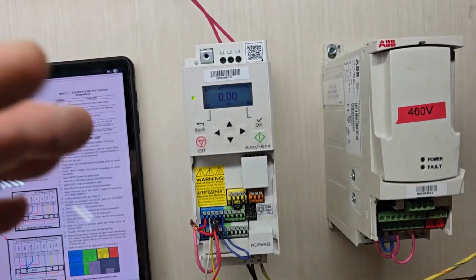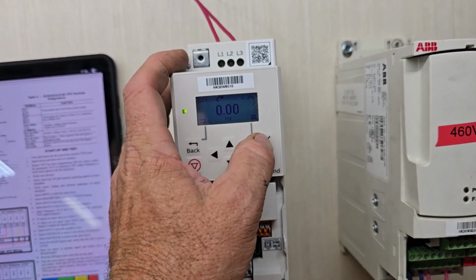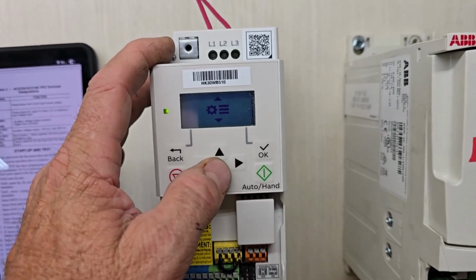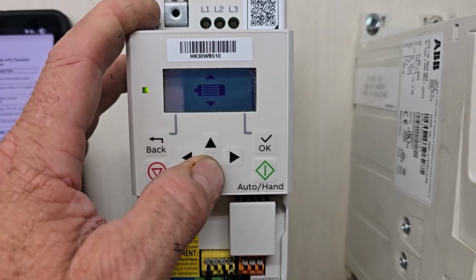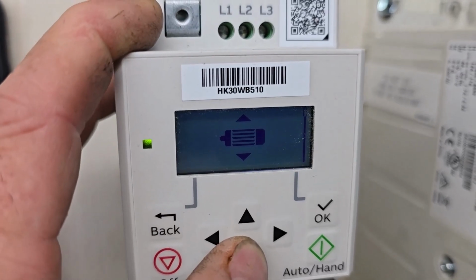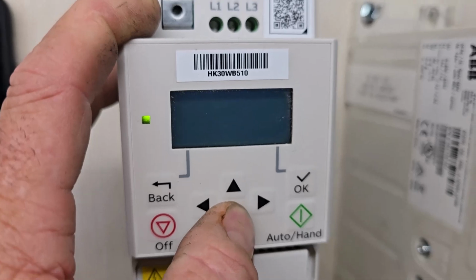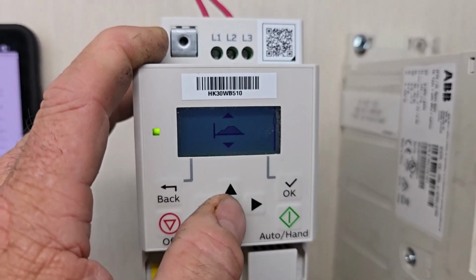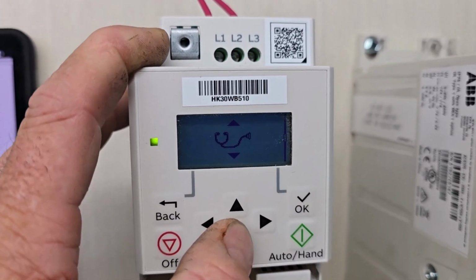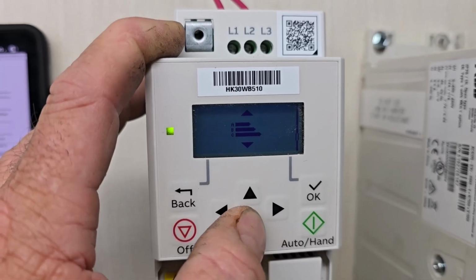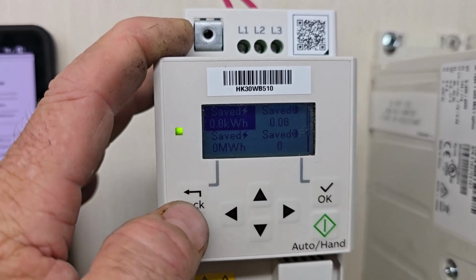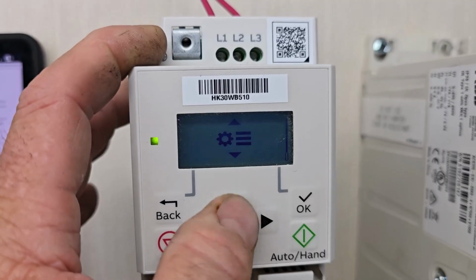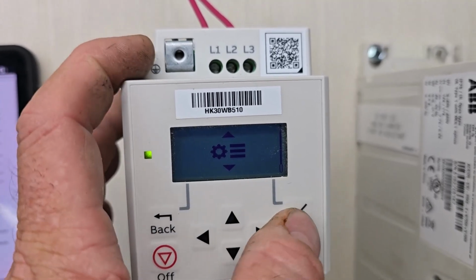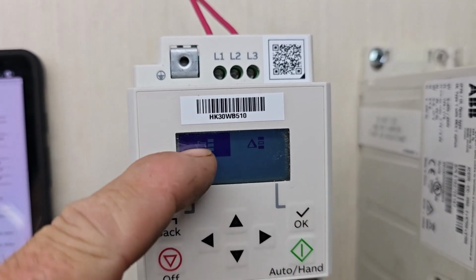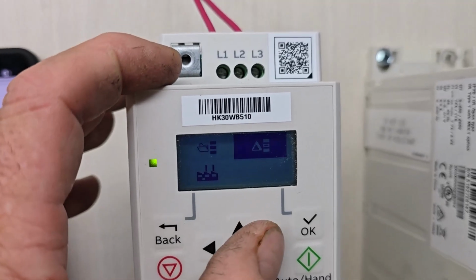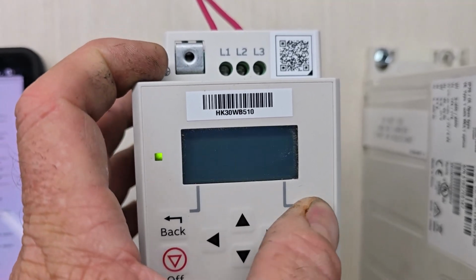So I've got this powered up, but one thing I want to do is restore this to factory default since I already programmed it. So here's your first little icon, and this is what's frustrating, the icons. Well, that's motor settings, and here's your scaler, your delays and stuff. Here's your troubleshooting one, diagnostics, I forget what this one was, some other settings. But then you want to get down here where it shows a wrench and the hamburger button, that's your settings. Normally we're going to want to go to the full settings. These are change settings, but down here is factory reset.